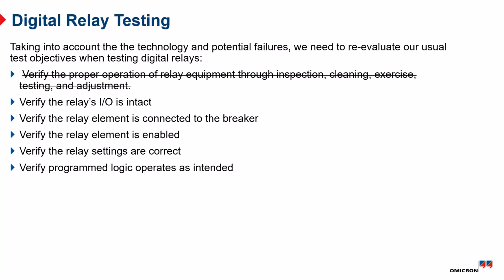The relay had gone through a number of different testing cycles and been retested, but each time they downloaded the settings of the relay and tested the relay against those settings. Nobody ever really looked at the settings and what was in there, and didn't notice that the phase distance was disabled.